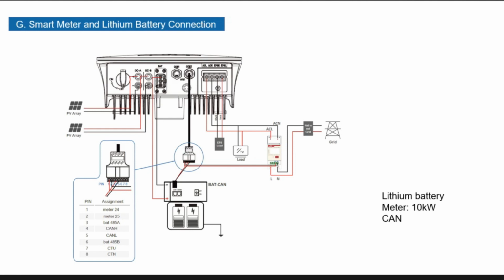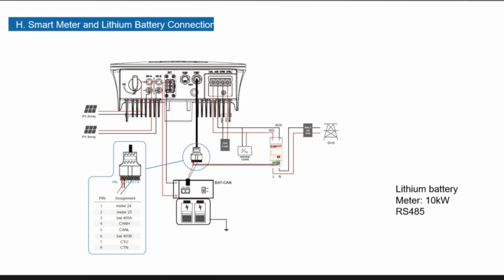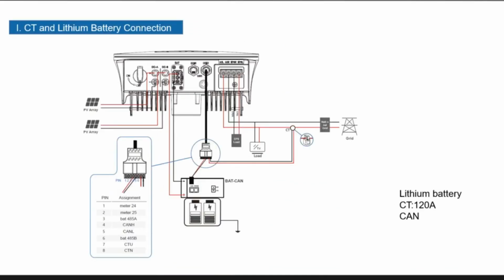And it will measure the voltage to give you the percentage of the battery charge. It's a bit of a crude way of doing it. This could do that, but I wouldn't really advise it. You can set the upper end limit of the voltage of the batteries and the lower end limit of the voltage of the batteries, and also the charge and discharge rate can be set within software as well. So it will work without communicating. You can do it, but I don't advise it.